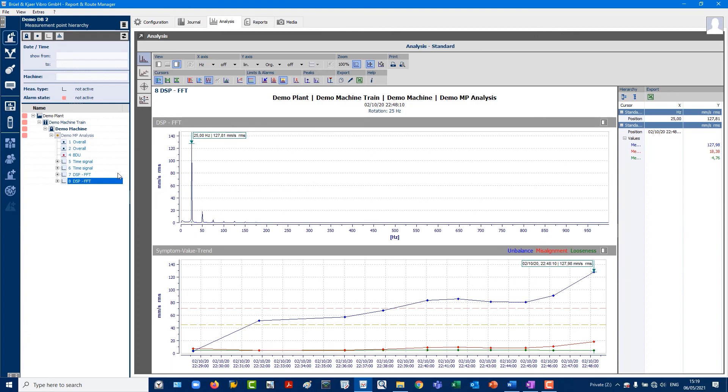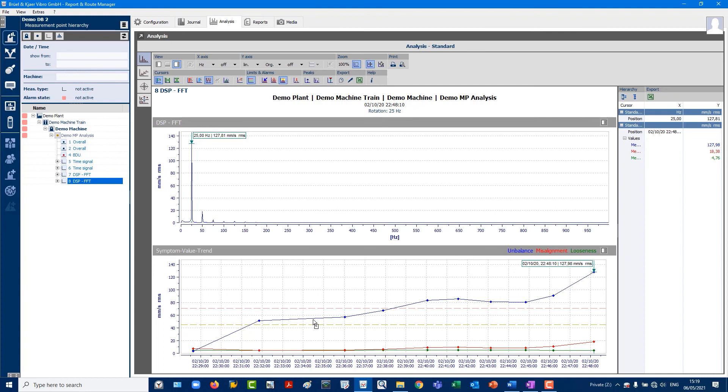We now move on to the DSP, the Digital Signal Post Processing, which in our example we have also configured to look at either spectral data or the specific FFT. Above, you can see the FFTs. Below, we are offered to calculate the trends of 1x, typically unbalance, 2x, typically misalignment, 3x, for example, looseness.